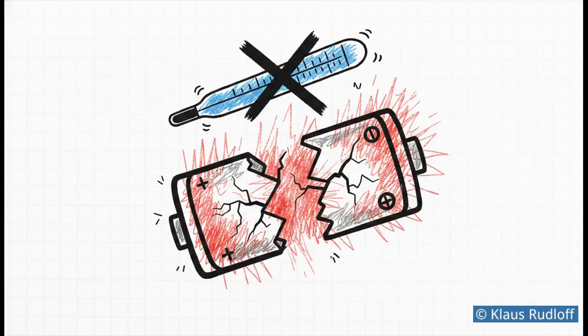So the ultimate takeaway from our sources is incredibly stark. For experienced system architects, designing your system solely around these datasheet averages is practically begging for premature, localized degradation. You simply cannot manage a high-density 5+ megawatt-hour container by just looking at the average temperature. You absolutely have to design for the extremes hiding in the center of the rack.